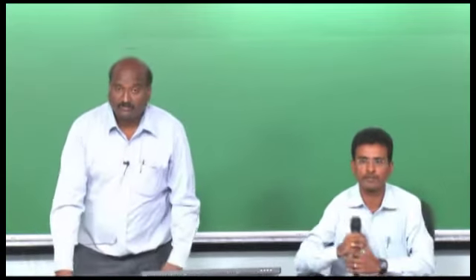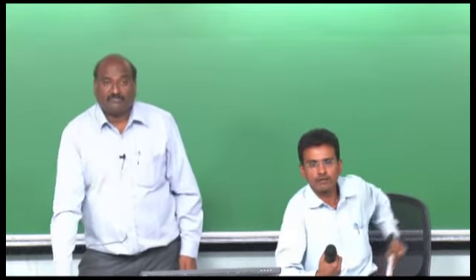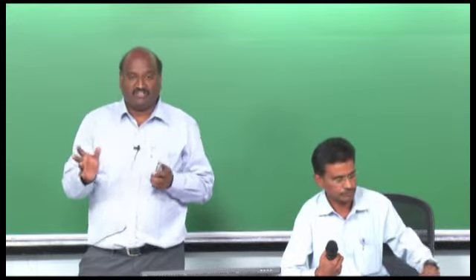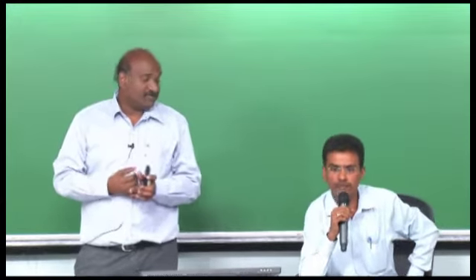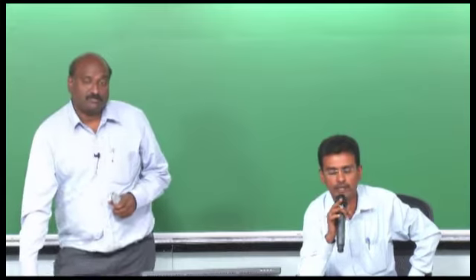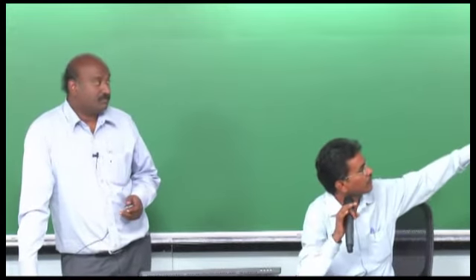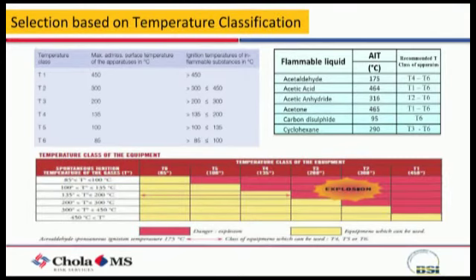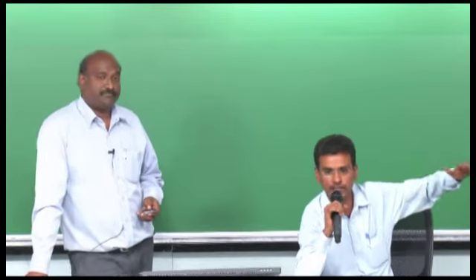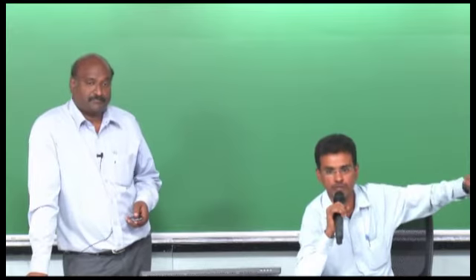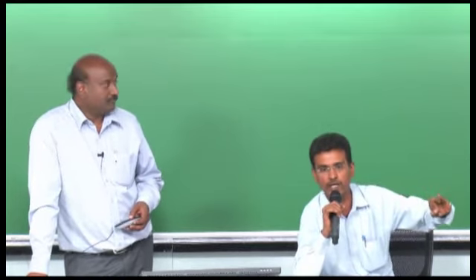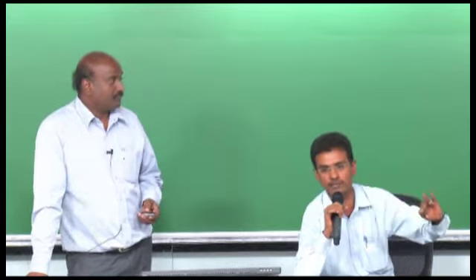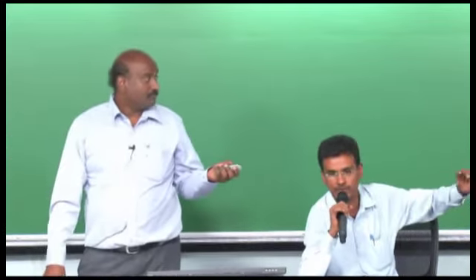When selecting equipment, three things must be considered: what is the zone, what is the AIT of the flammable liquid or solvent being handled, and what is the gas group. If handling multiple solvents, select based on the minimum AIT — whichever chemical has the least auto ignition temperature determines the equipment selection. For petrol or diesel, AIT is around 200 degrees, so normally equipment of T4 or T5 is selected.